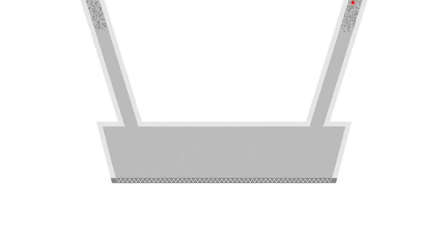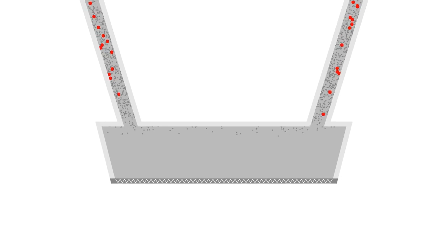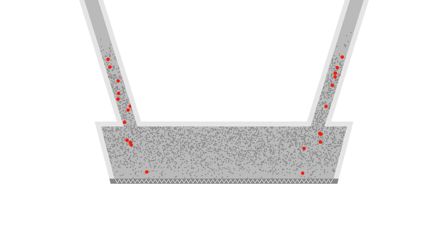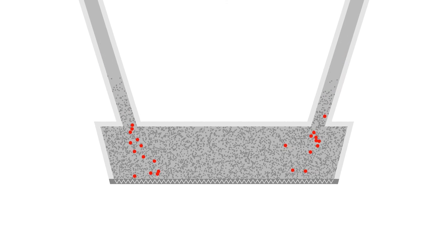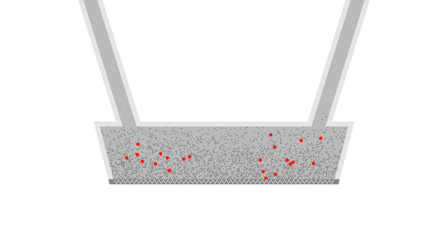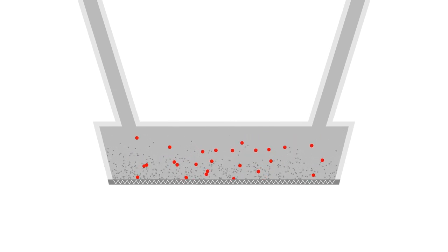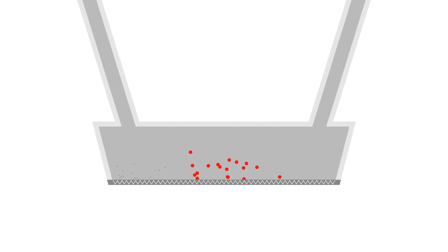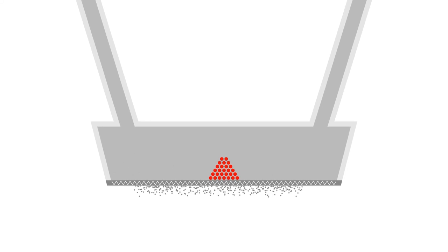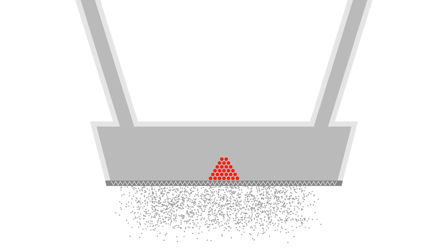Samples are introduced into one or both channels. They then flow downward toward a molecular weight cutoff membrane available with a variety of molecular weight cutoffs. Analytes accumulate above the membrane, where flows cancel, concentrating and washing the retained biomolecules. Meanwhile, buffer fluid and small molecules pass through the membrane to the waste port.